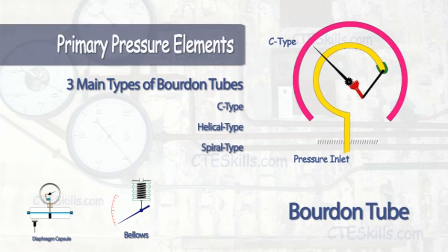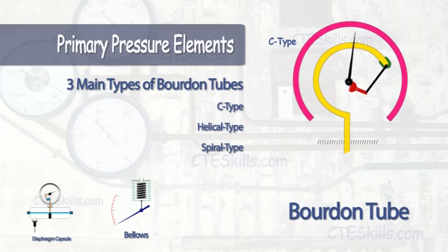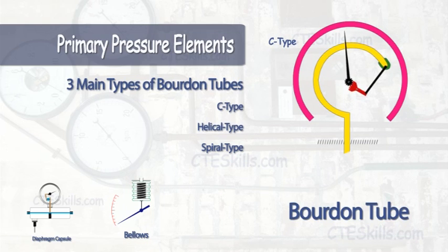The pressure inlet is attached to one end of a tube. A mechanical linkage connects the other end of the tube to a pointer. Changes in pressure will cause the tube to contract and expand, which causes the pointer to move respectively.